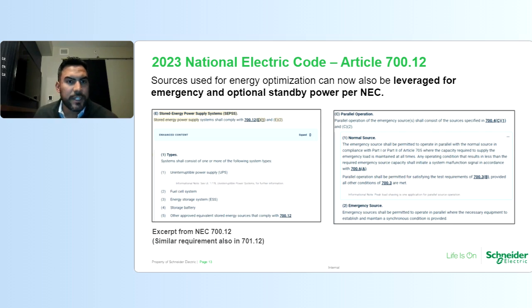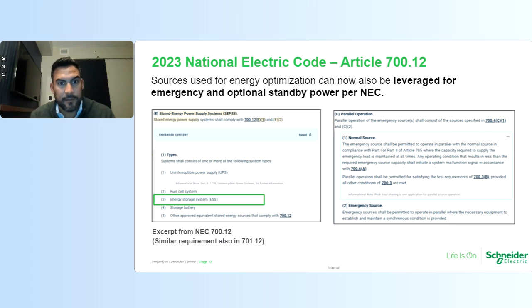So we're going to jump into the National Electric Code, and I'm going to highlight Article 700.12, where it now highlights where energy storage systems can be used as an acceptable means for emergency and optional standby power. Before 2023, I used to get the question quite frequently, well, Benny, can we use energy storage systems for emergency power? In the 2023 National Electric Code, they have now implemented that. So whether that's battery, or some different type of chemical technology, it could be used for an emergency system. In addition, it references that if you use this energy storage system in parallel operation with the normal source, you can use that on-site energy asset and energy storage system for emergency power.